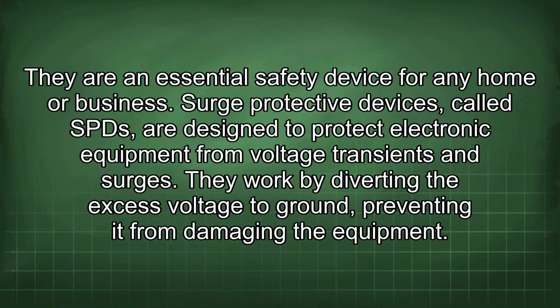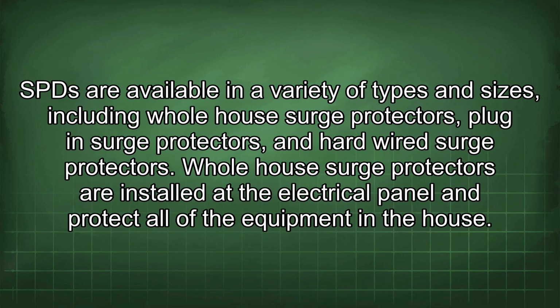Surge protective devices, called SPD, are designed to protect electronic equipment from voltage transients and surges. They work by diverting the excess voltage to ground, preventing it from damaging the equipment.